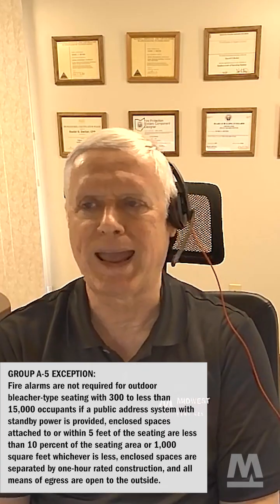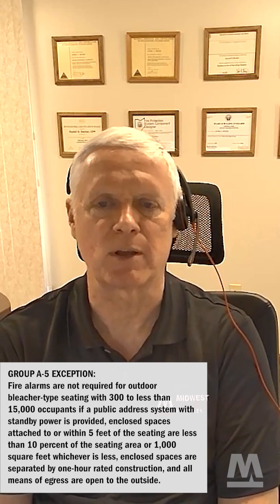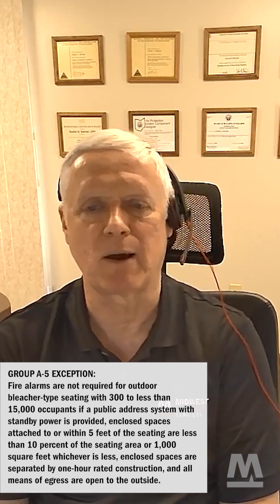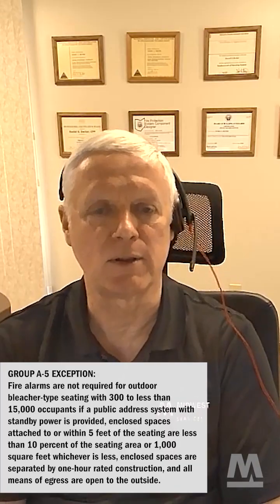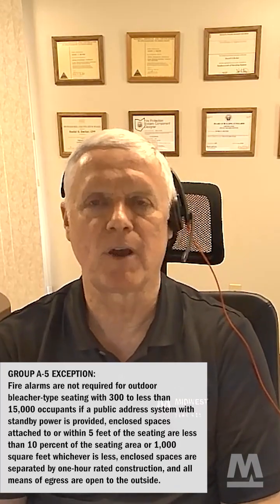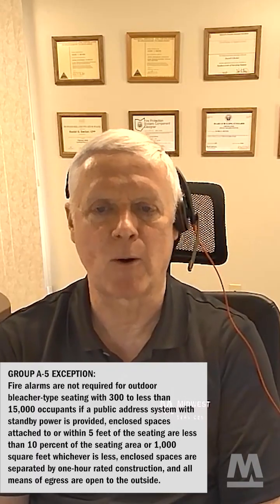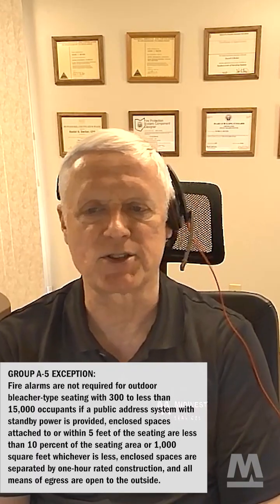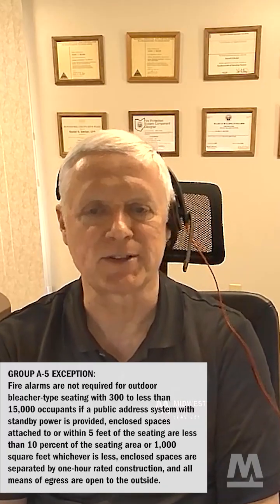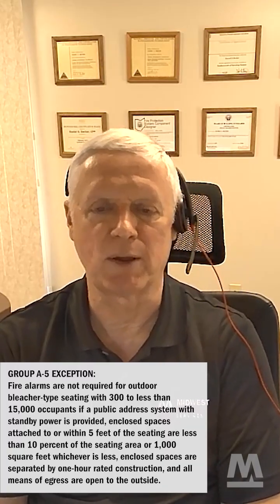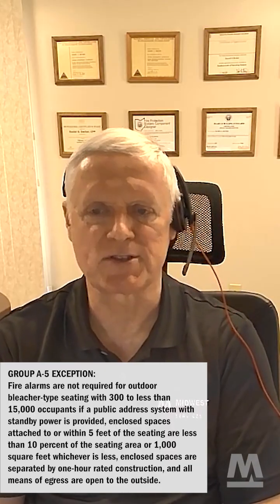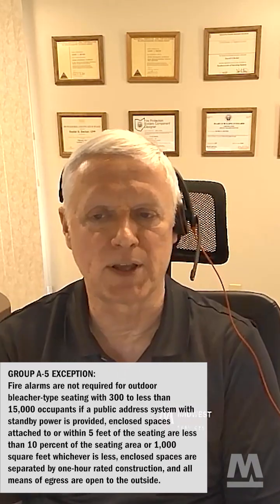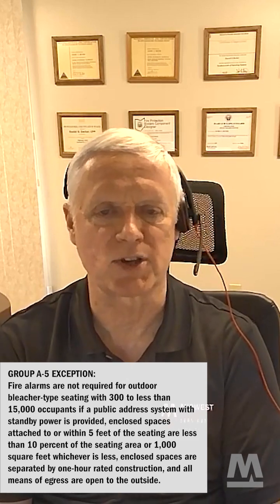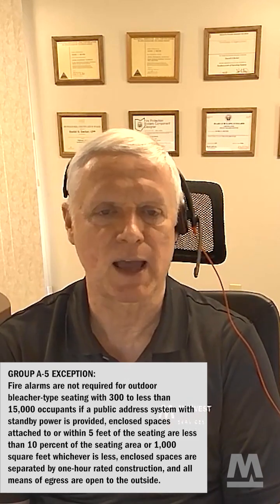If you've got a Group A5, which is an outdoor bleacher exception, the fire alarm is not required for outdoor bleacher type seating with 300 to less than 15,000 occupants if they've got a PA system with standby power, and enclosed spaces that are attached to or within 5 feet of seating are less than 10% of the seating area, or 1,000 square feet, whichever is less. The enclosed spaces that are associated with the outdoor bleachers have to be separated by a 1 hour rated construction, and all means of egress are open to the outside. So for the most part, your typical high school football stadium is not going to require a fire alarm system.